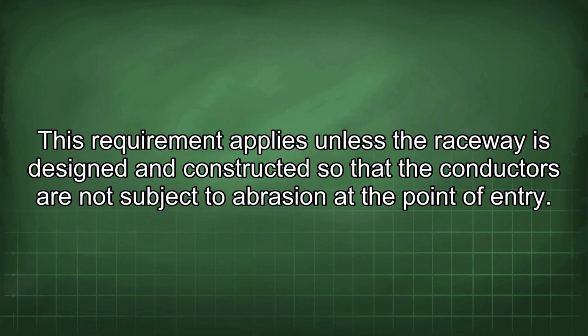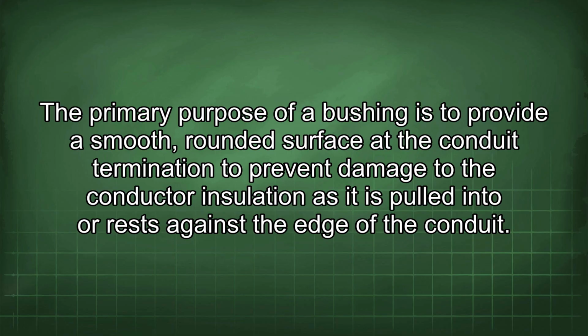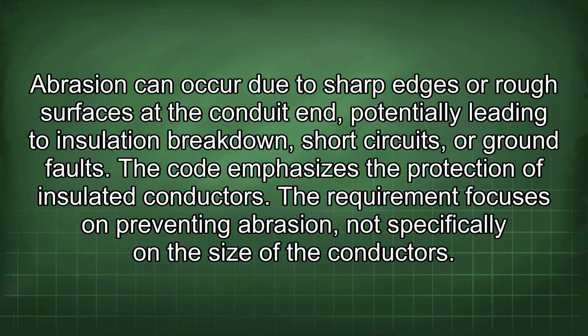This requirement applies unless the raceway is designed and constructed so that the conductors are not subject to abrasion at the point of entry. The primary purpose of a bushing is to provide a smooth, rounded surface at the conduit termination to prevent damage to the conductor insulation as it is pulled into or rests against the edge of the conduit. Abrasion can occur due to sharp edges or rough surfaces at the conduit end, potentially leading to insulation breakdown, short circuits, or ground faults.